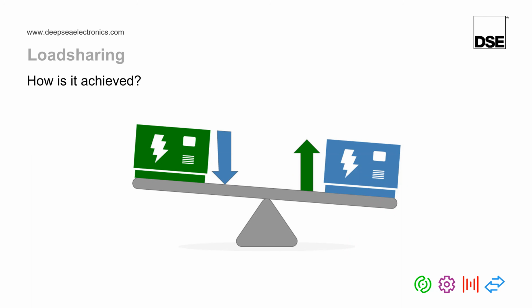So for example, imagine you had a 100 kilowatt load and you had two generators. One was 200 kilowatts and one was 100 kilowatts. The way this would work is the 200 kilowatt generator would produce 66 kilowatts and the 100 kilowatt generator would produce 33 kilowatts. But the net result is that both generators would be producing 33% of their size. So again, when load sharing, what the DeepSea module tries to do is make sure that the generators are producing the same percentage of power, not necessarily the same amount of power.